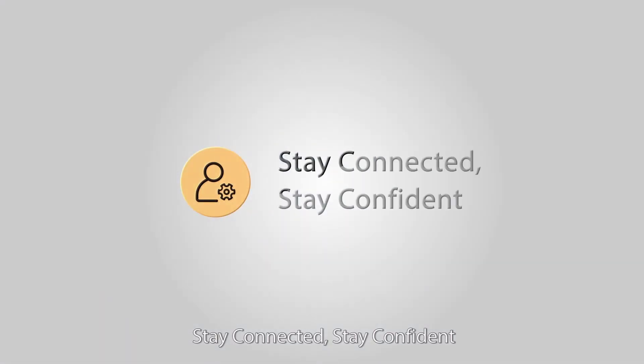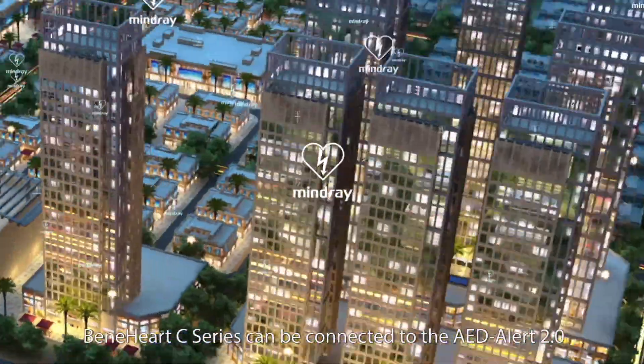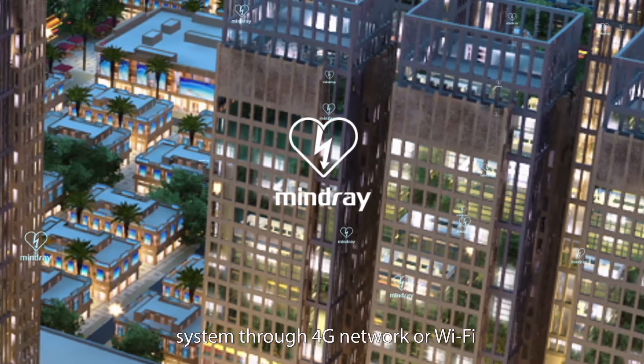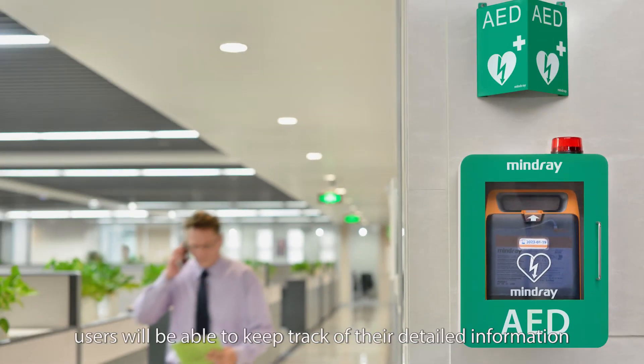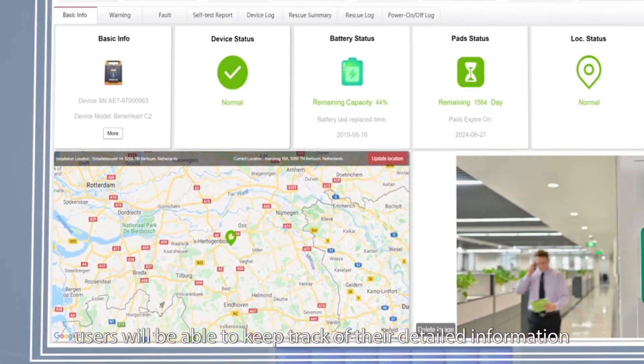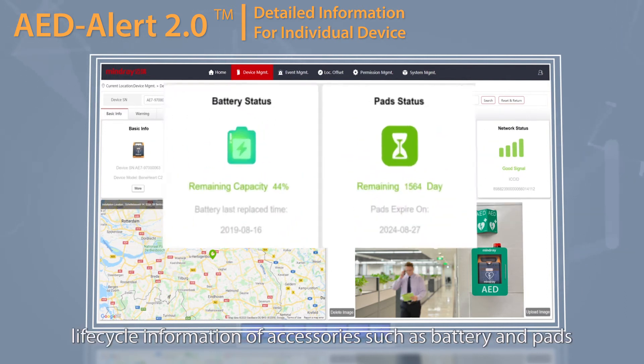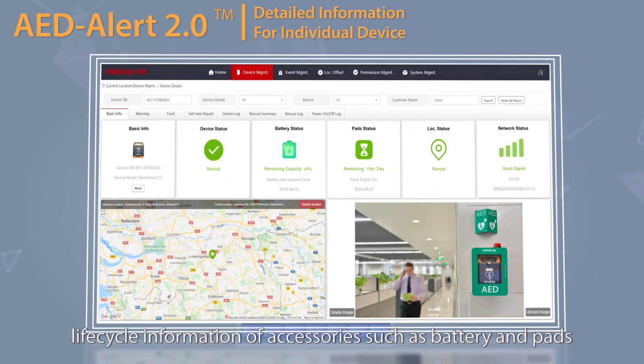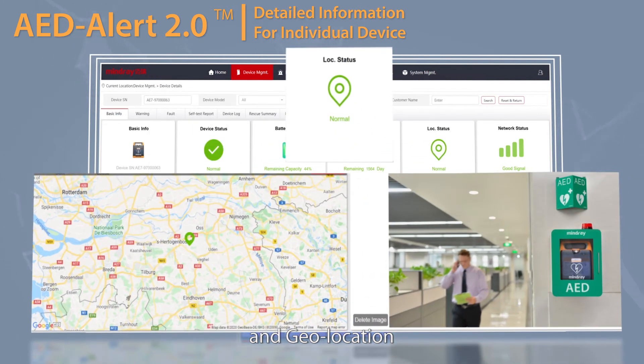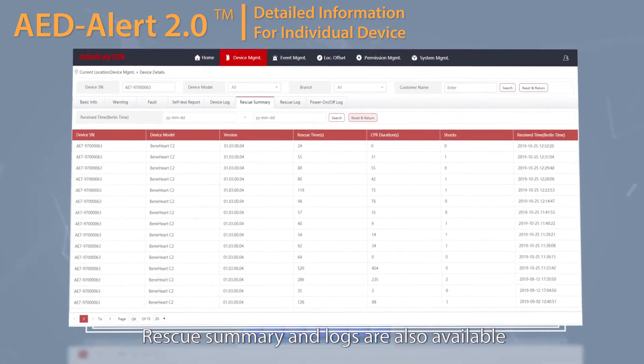Stay connected. Stay confident. The BeneHeart C-Series can be connected to the AED Alert 2.0 system through 4G network or Wi-Fi. For individual devices, users are able to keep track of detailed information, including device working and network status, life cycle information of accessories such as battery and pads, geolocation, as well as rescue summaries and logs.